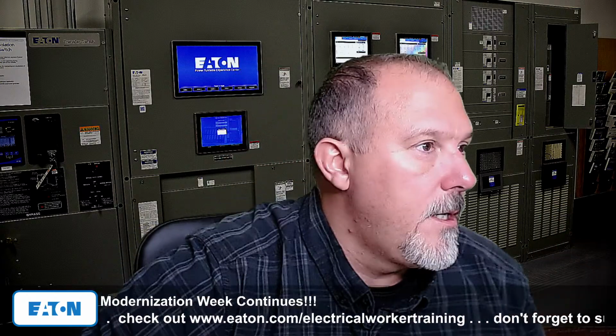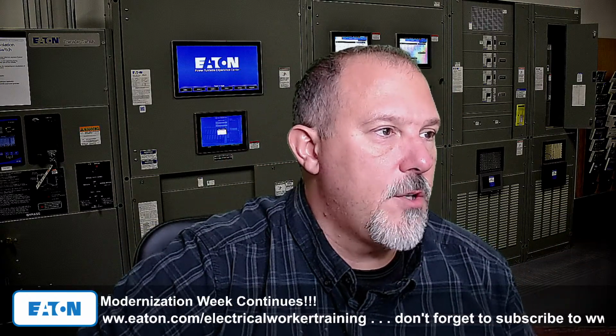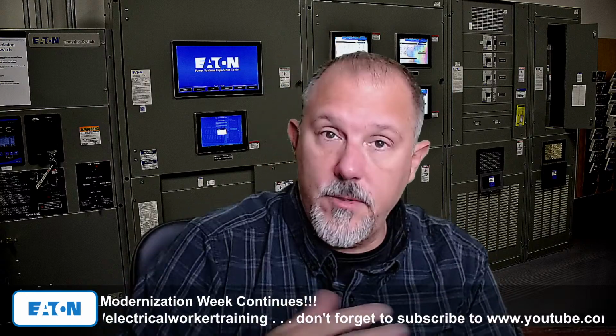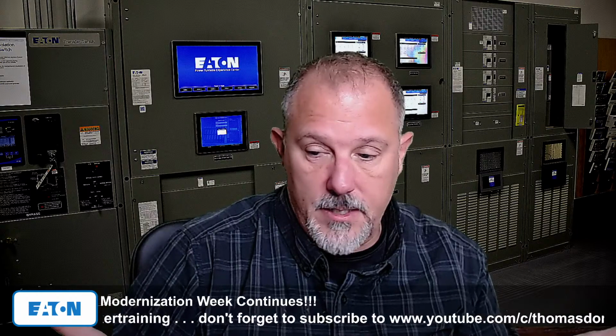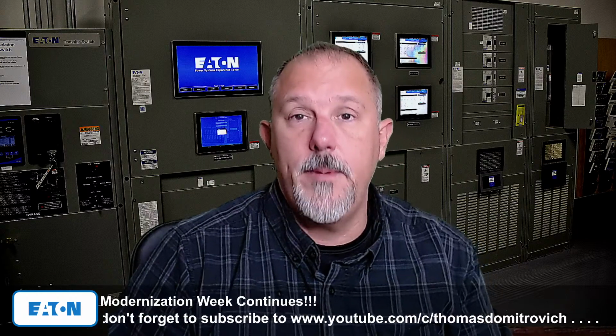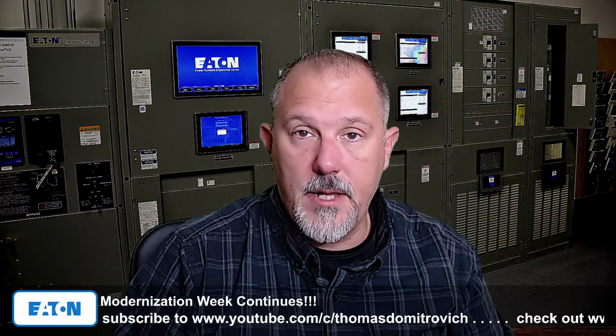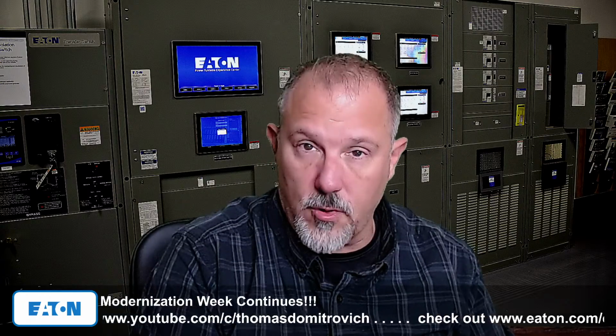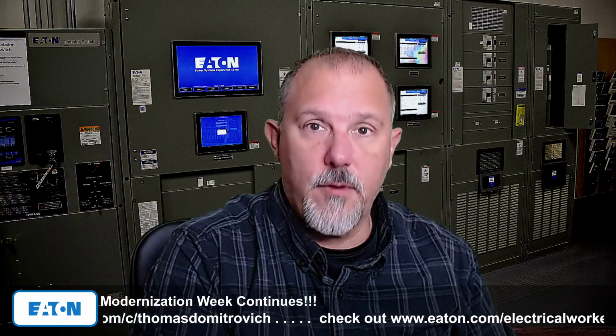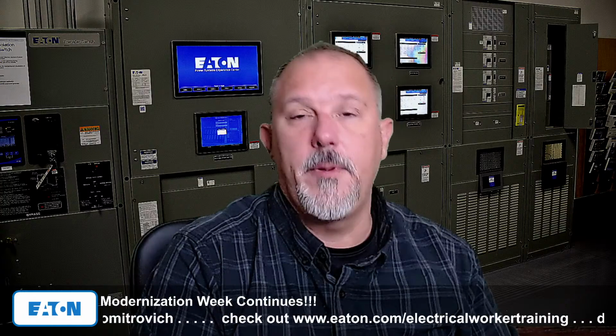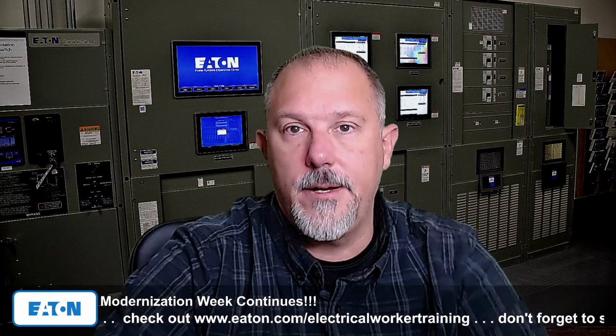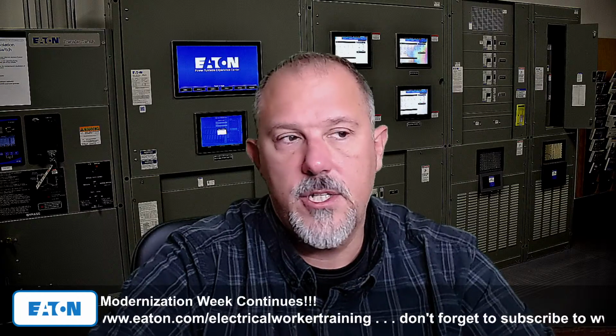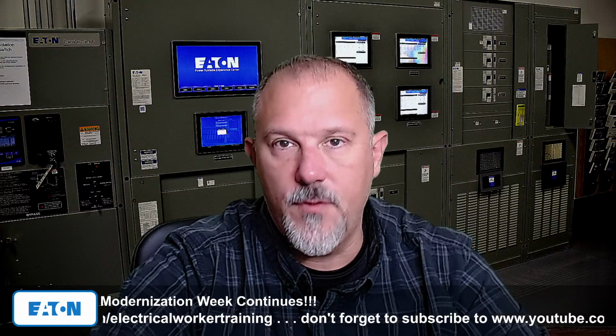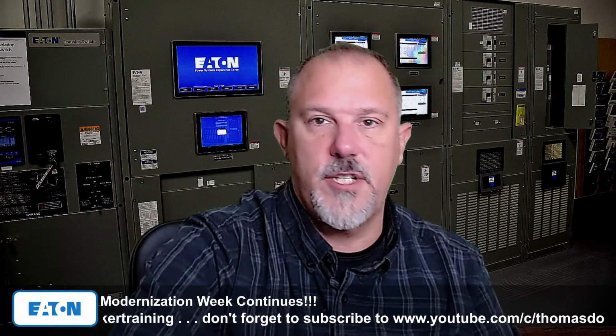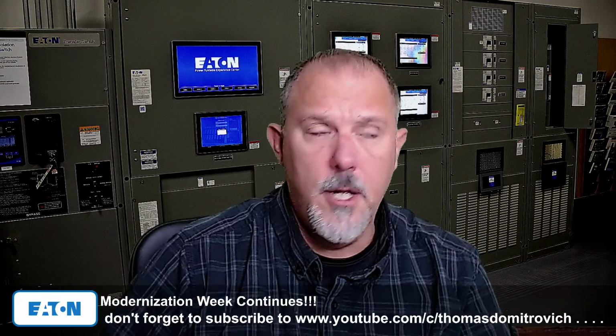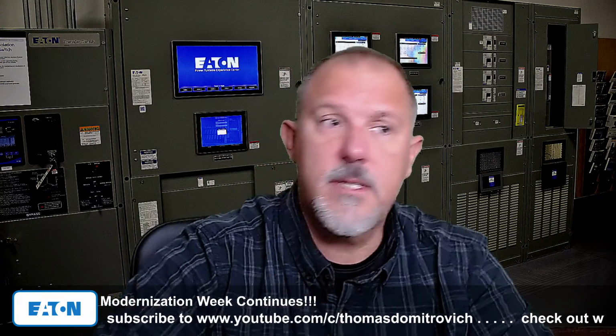Anyway, I'll get on my soapbox. Now, what I would suggest, and some people, this is a debatable item, I would suggest putting ground fault protection of equipment on it. Put GFPE at 30 milliamps. You at least have something so that if there's a short out there, if a ground fault current is flowing, you're going to probably be greater than 30 milliamps. The one that killed that child was definitely greater than 30 milliamps. So you can isolate a problem before somebody touches it if you provide some level of protection outside of the thermomagnetic circuit breaker. So GFPE is some level of additional protection.